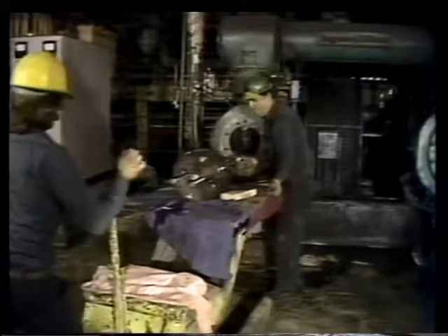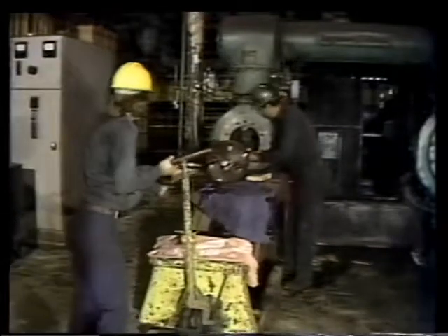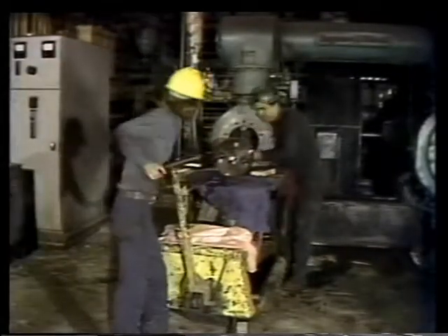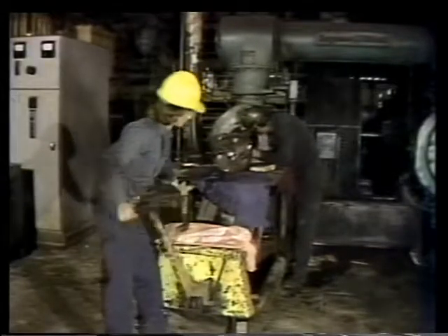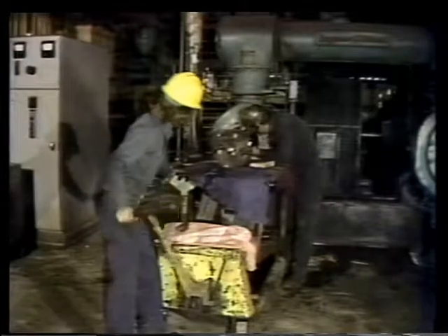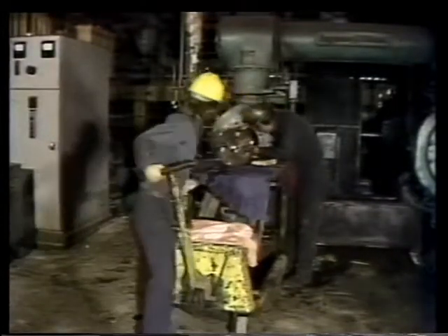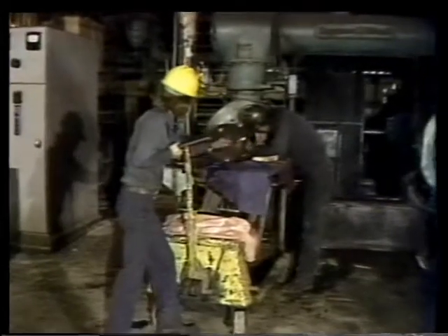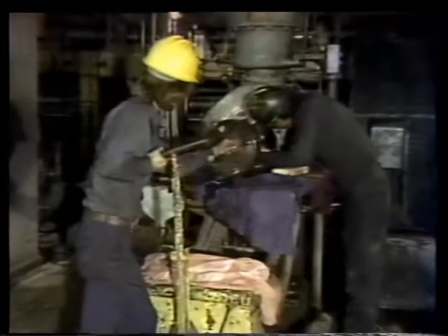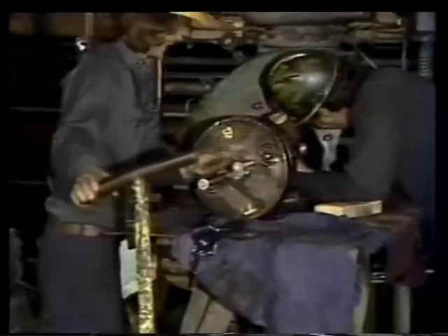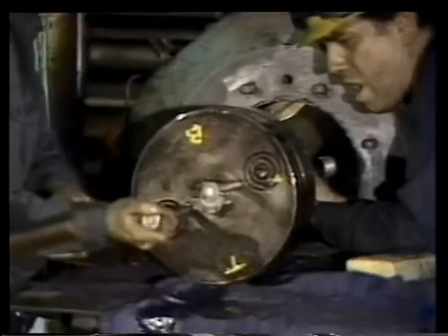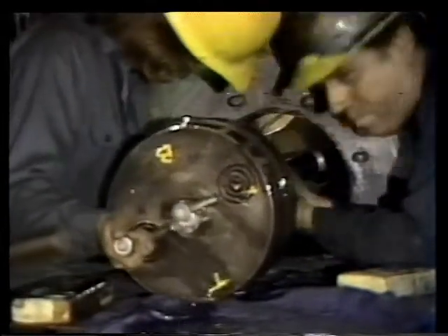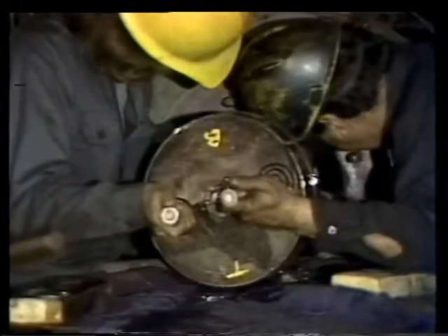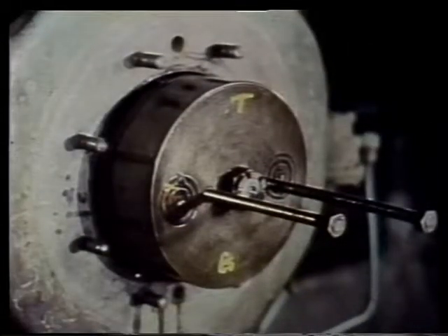Now you're ready to put the piston into the cylinder. It usually takes more than one person to do this. You might want to use a portable table to support the piston assembly. Slide the piston into the cylinder up to the point of the rings. Be careful not to let the rings hit the cylinder. If they bump against the cylinder, they could break.